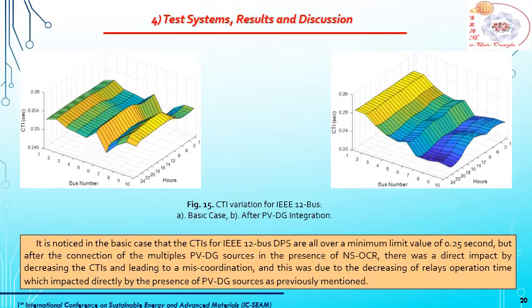Figure 15 represents the coordination time interval variation for the first test system. It is noticed after the integration of PVDG sources in presence of non-standard overcurrent relay that there was a direct impact by decreasing the CTI under a minimum limit value of 0.25 seconds and leading to miscoordination.